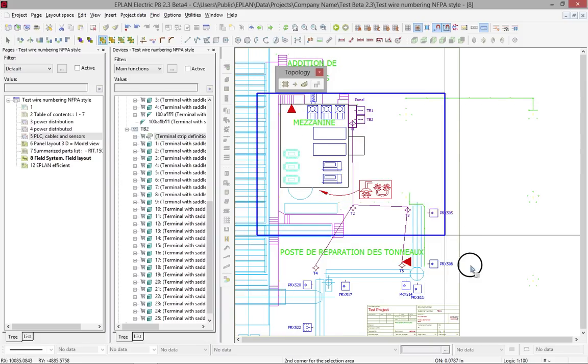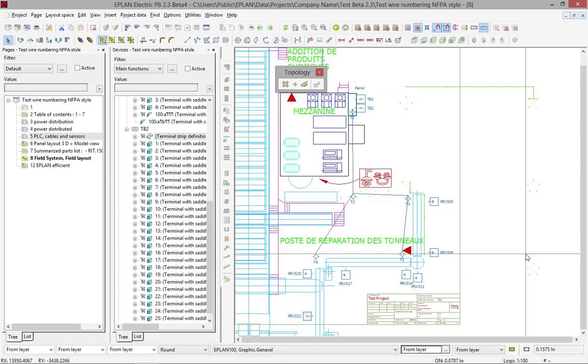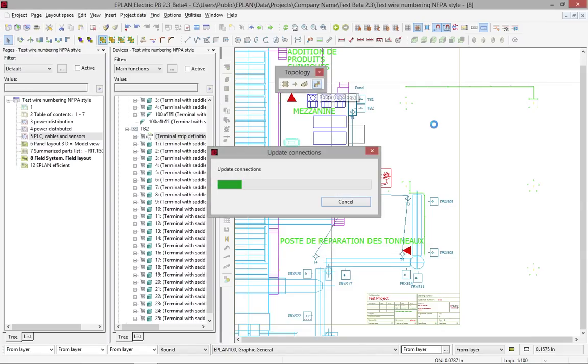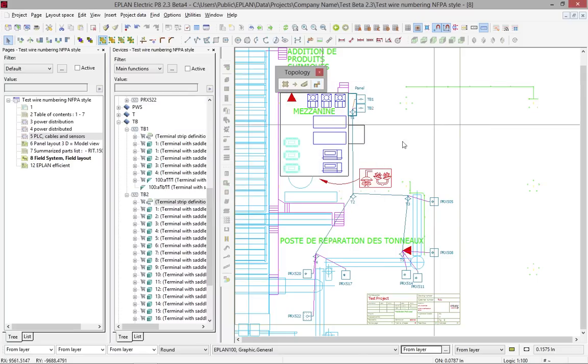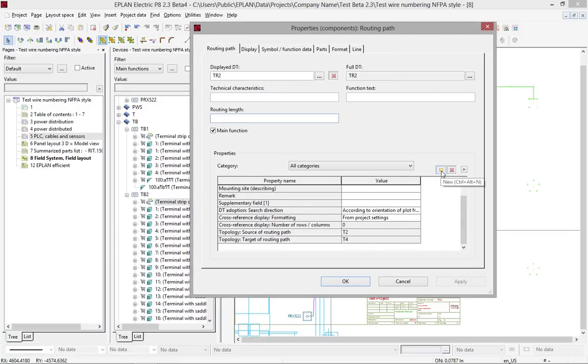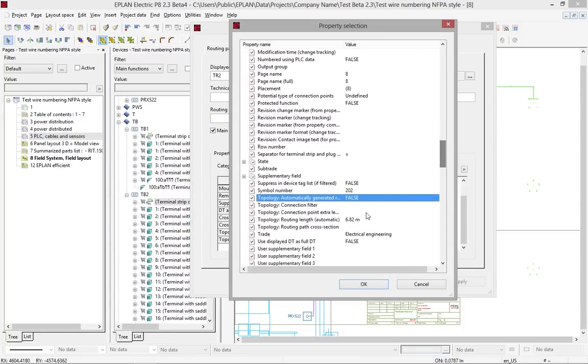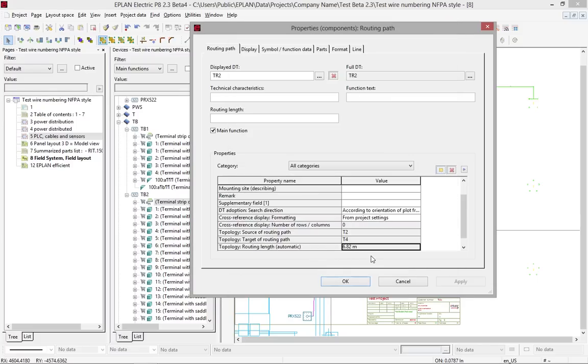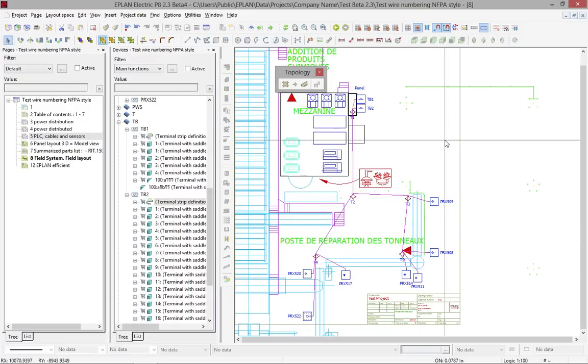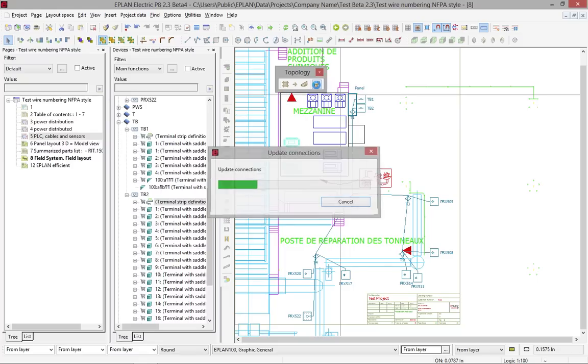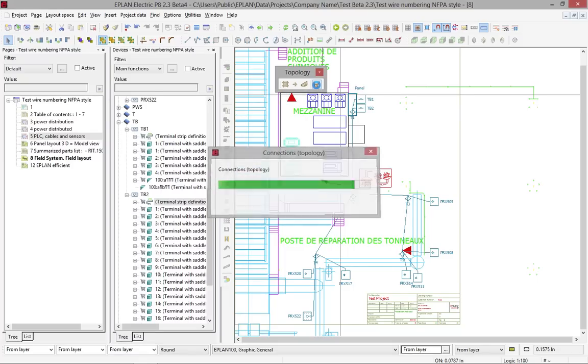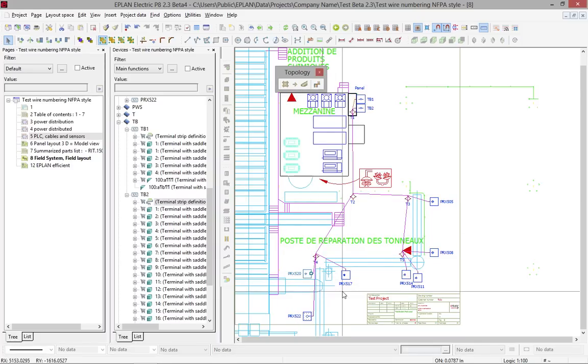Once this is done, you select all your items, your objects, including the routing path and the routing points, and you run the route topology tool. What this actually does, it tries to figure out where is the shortest route to go through each of these elements. Every one of these cable trays, tray 1, tray 2, tray 3, have a specific length that was assigned to them. It's actually the topology routing length. The automatic length is the one-to-one length calculated out of this environment. But if you know you have to go through a few curves, you can modify this and say it's 8 meters instead of 6.2 meters. It adds up all the different lengths together from the different trays and this will be transferred to either the wires or to the cables that are on the other side in the schematics.